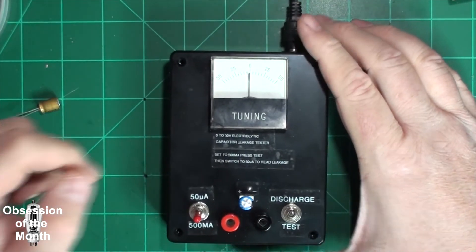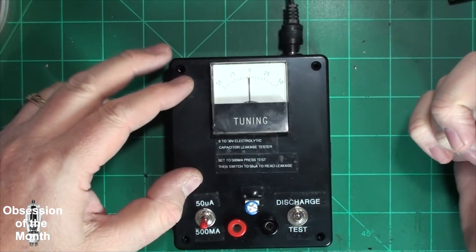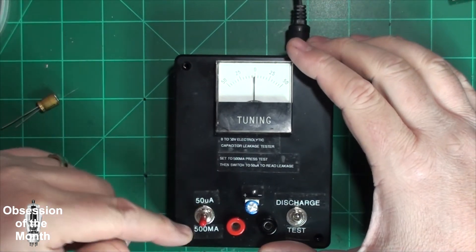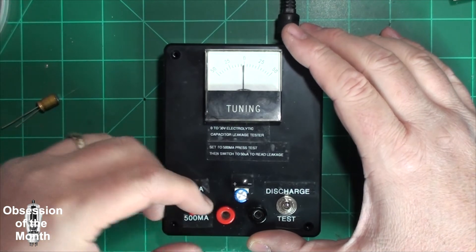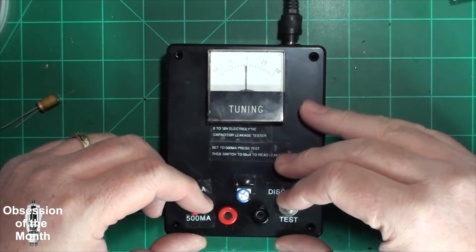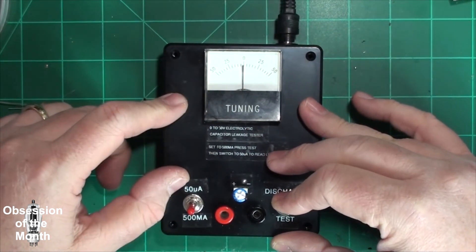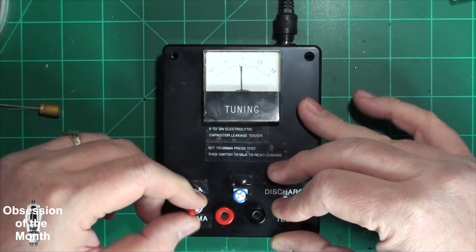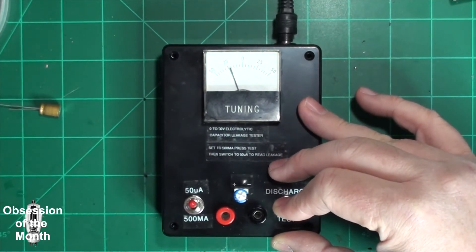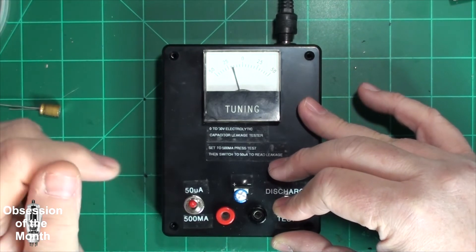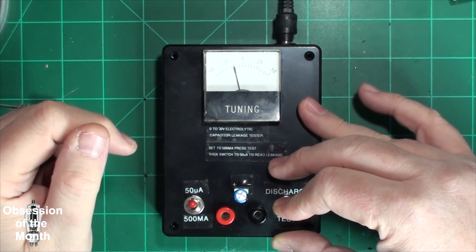So to do this, like I said we've got our voltage on. I've got this set to 500 milliamps. And then just set it to test. And you'll see the needle jump. And then you move it to 50 microamps. And it shows you if there's any leakage.